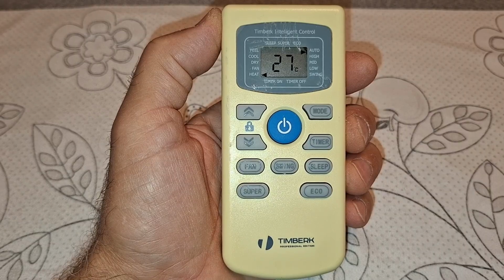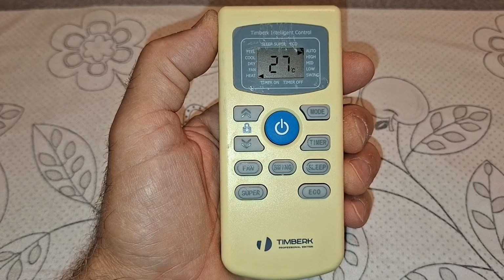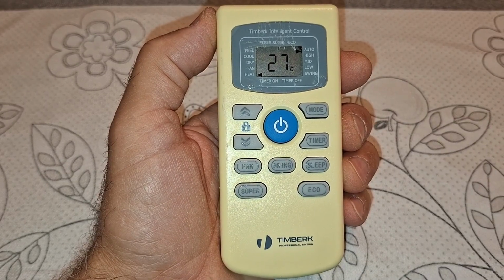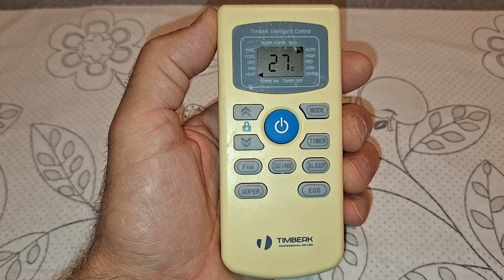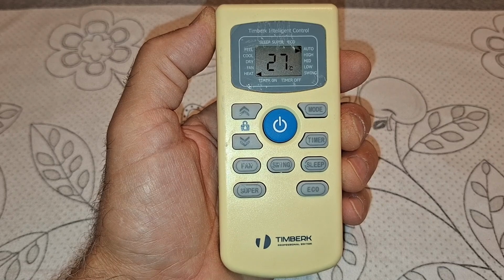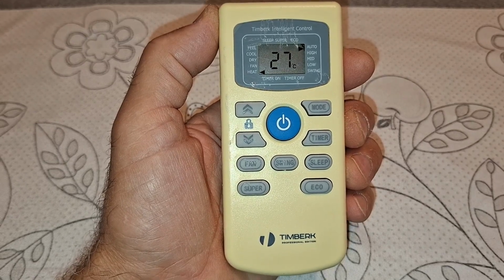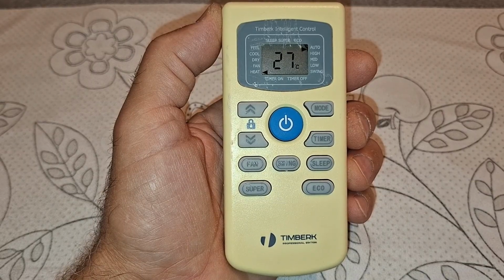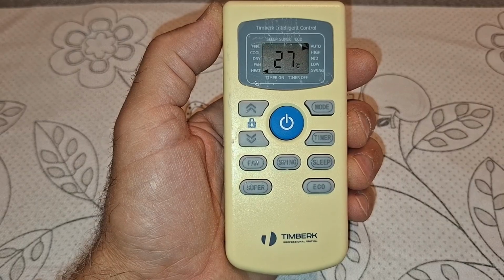In this mode, we set the temperature above 26 degrees Celsius. Setting the fan speed in auto fan speed mode in heating mode allows the air conditioner to work more efficiently, because in this mode, the fan speed of the air conditioner is adjusted by the microprocessor according to the condensation temperature. For this reason, the outdoor unit of the air conditioner becomes covered with snow only when the air temperature approaches 0 degrees Celsius.